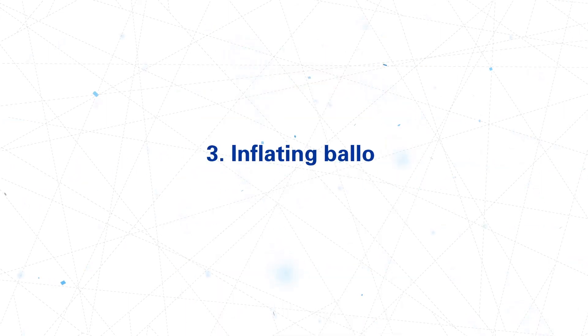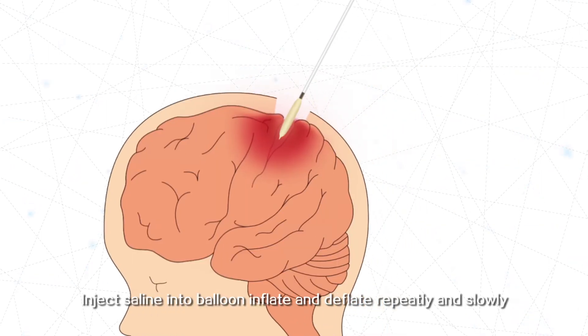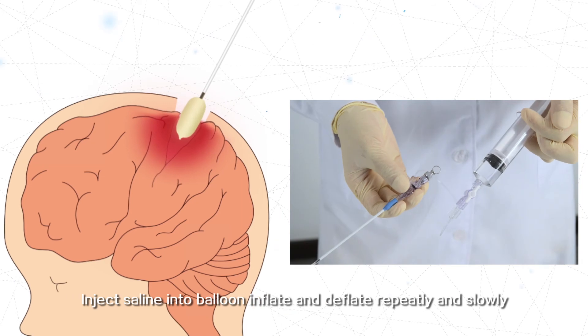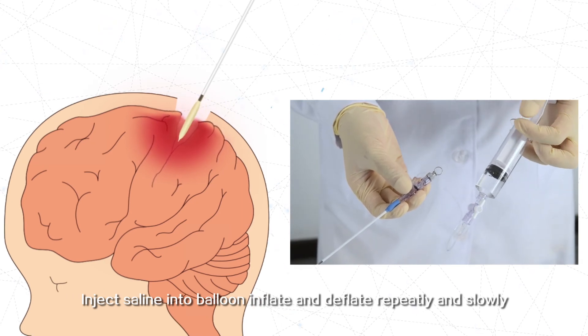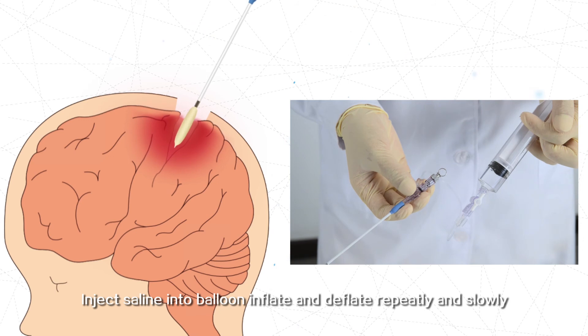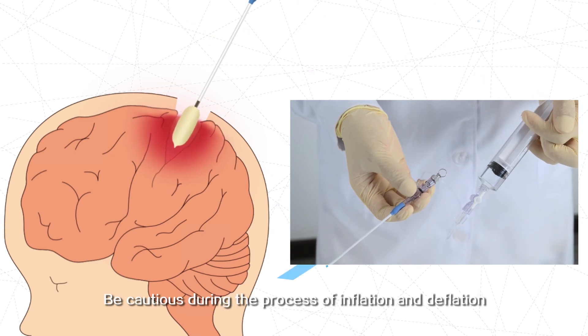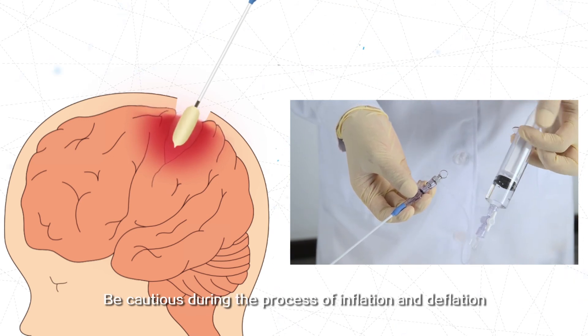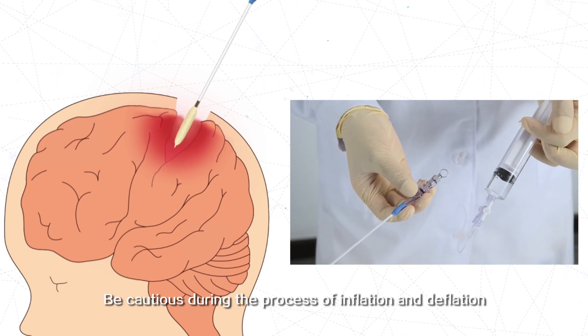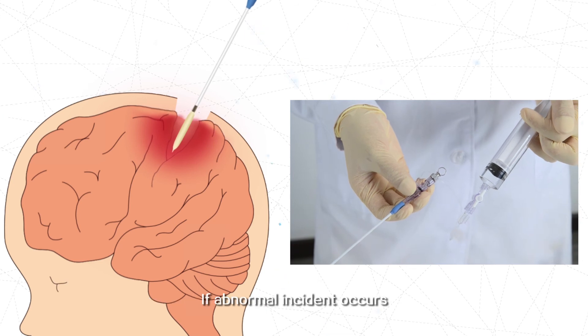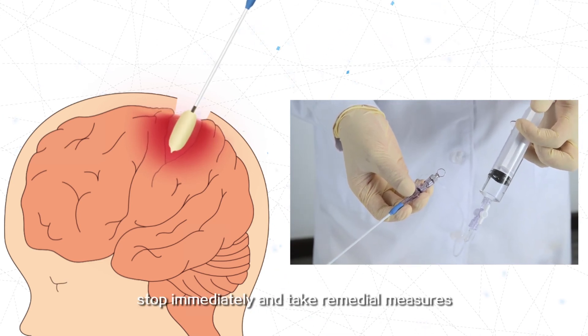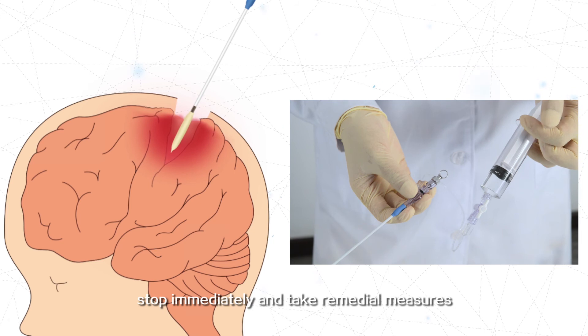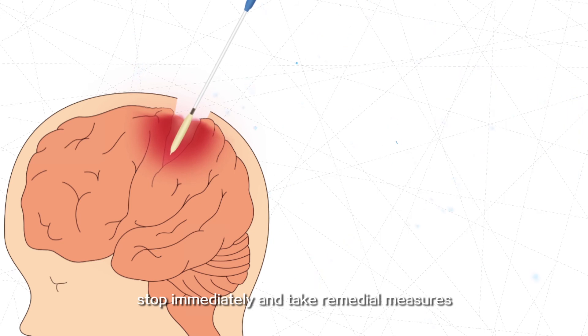Step 3: Inflating the balloon. Inject saline into the balloon and inflate and deflate repeatedly and slowly. Be cautious during the process of inflation and deflation. If an abnormal incident occurs, stop immediately and take remedial measures.